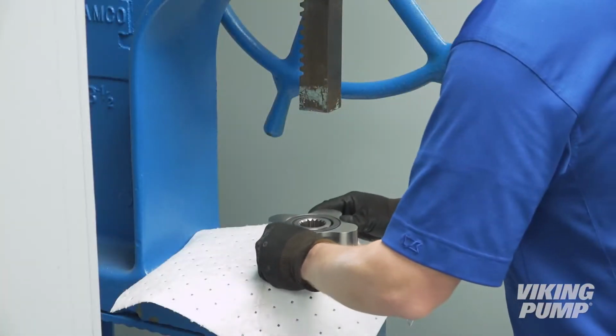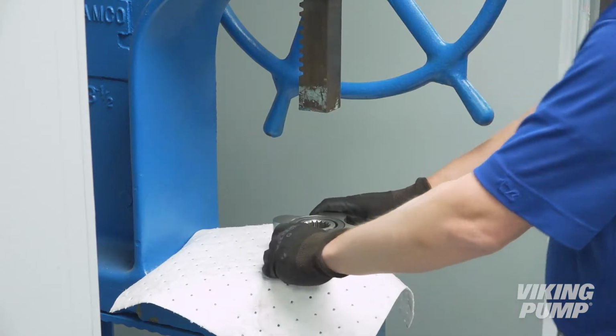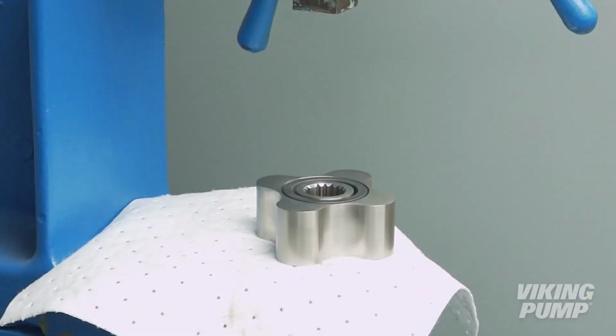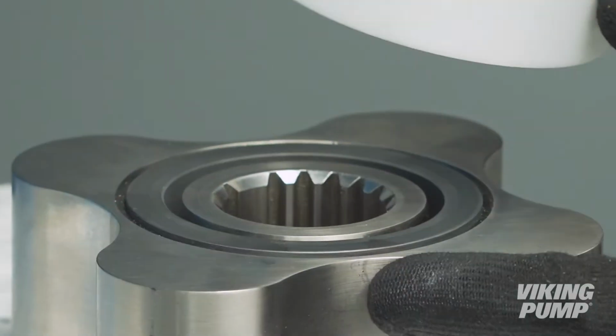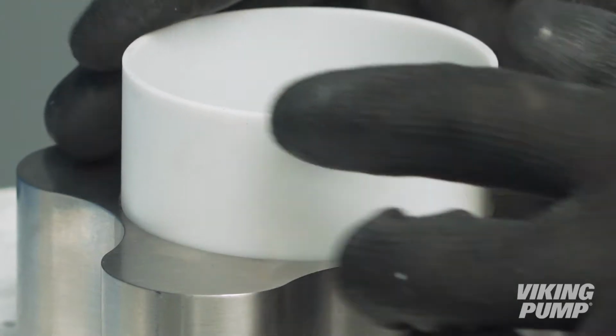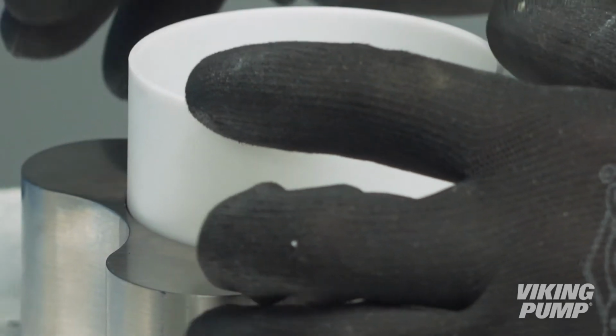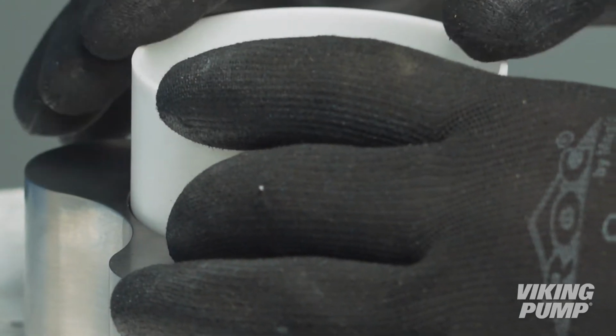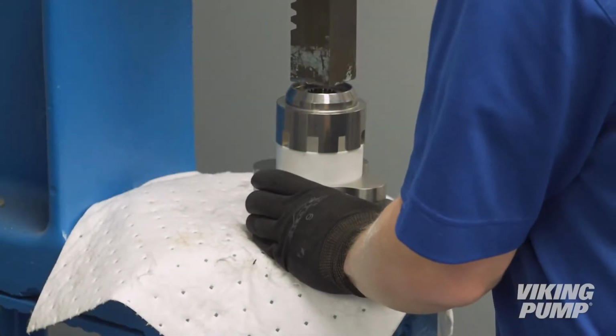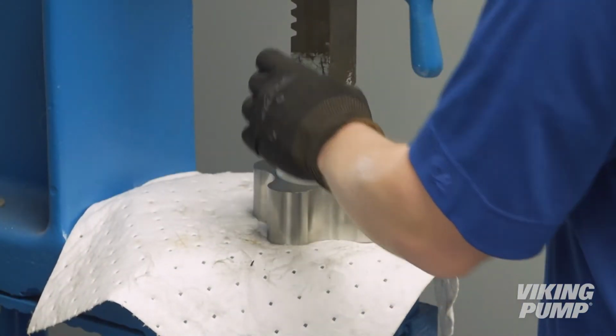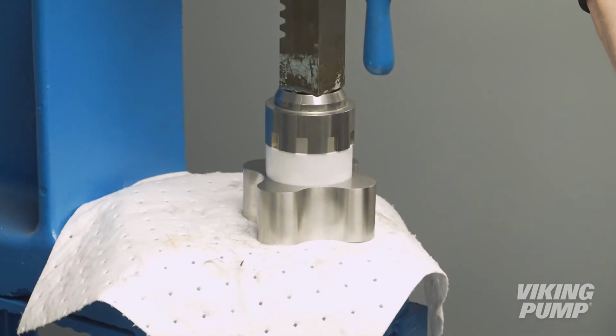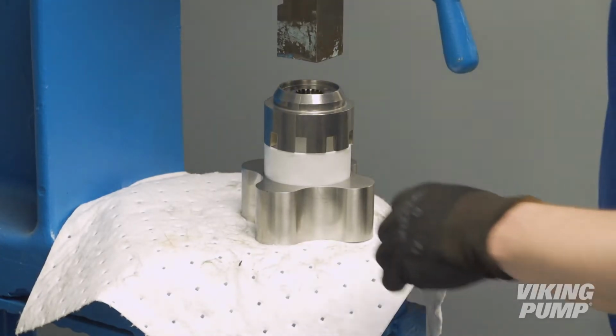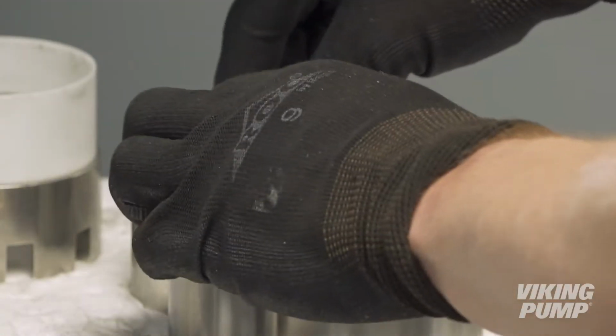Next, remove the rotary seal face from each rotor. To do this, place the rotor face down on an arbor press. Protect the rotor face by placing it on a piece of wood or cloth. Insert the provided seal face removal tool. Place it on the rubber cup around the seal face. Using an arbor of a greater diameter than the tool itself, press down on the tool. As the tool is forced downward, the rubber cup will force the seal face up and out of the bore.